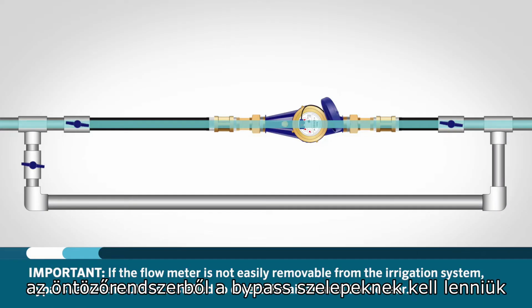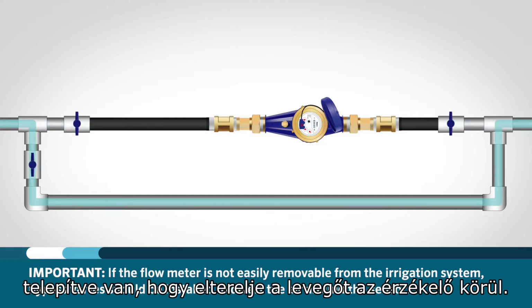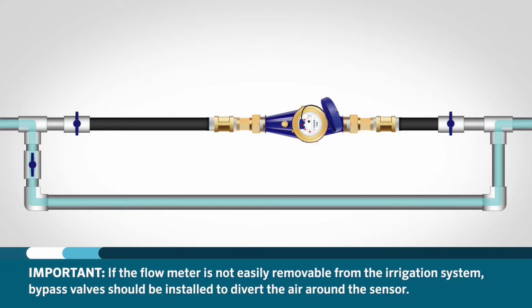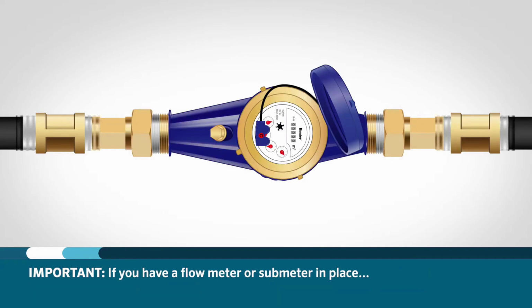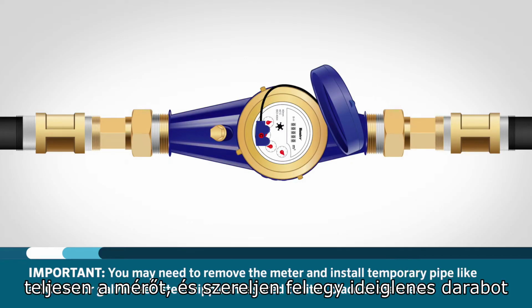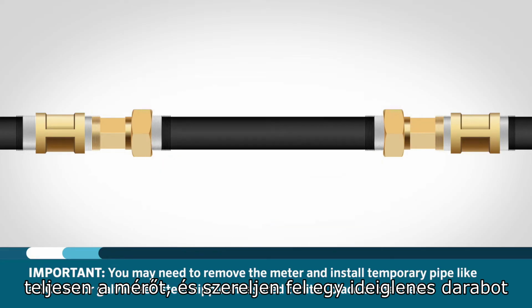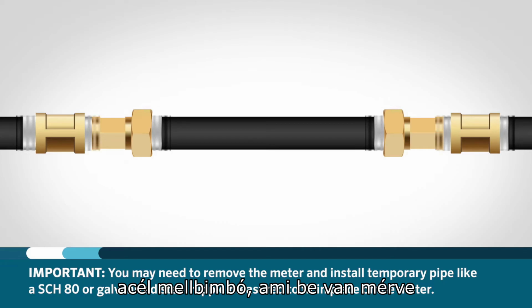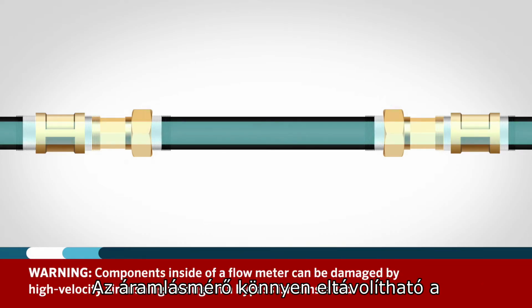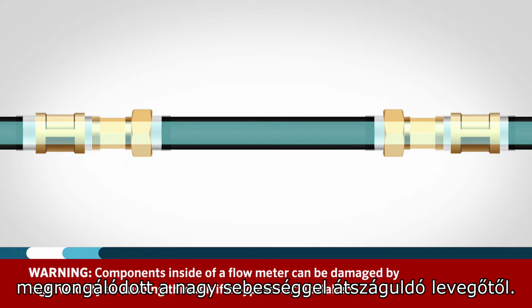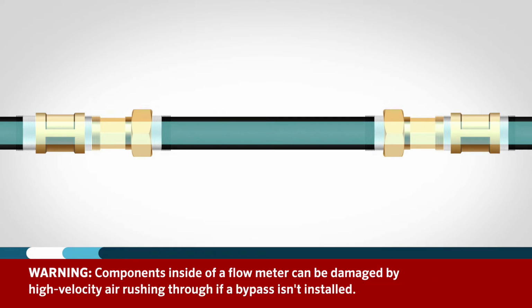If the flow meter is not easily removable from the irrigation system, bypass valves should be installed to divert the air around the sensor. If you have a flow meter or sub-meter in place, you may need to remove the meter entirely and install a temporary piece of pipe, like a Schedule 80 or galvanized steel nipple that is measured to fit in place of the meter. You do this because the components inside a flow meter can be easily damaged by high-velocity air rushing through.